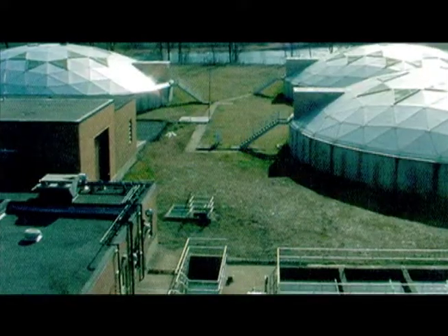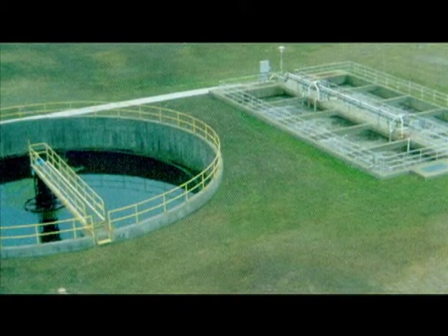And from there, the effluent from the primary is going to go to our trickling filters, which have organisms growing like an algae on a rock media. And that helps remove some phosphorus and organic food, what we call biological organics. And from there, that effluent is going to go off to our aeration tanks. There we have a mixed liquor with our organisms that continue to feed to help remove ammonia, nitrogen, phosphorus, and any more BODs that are in the wastewater.